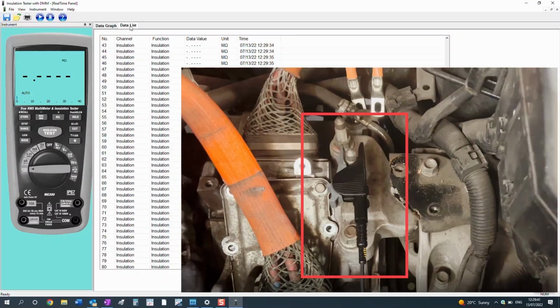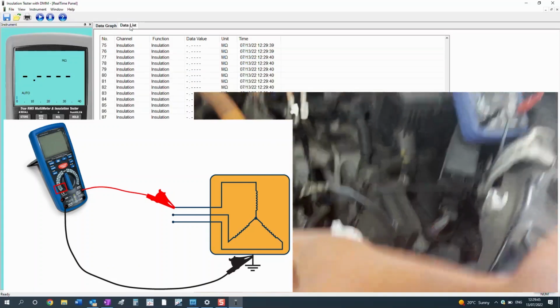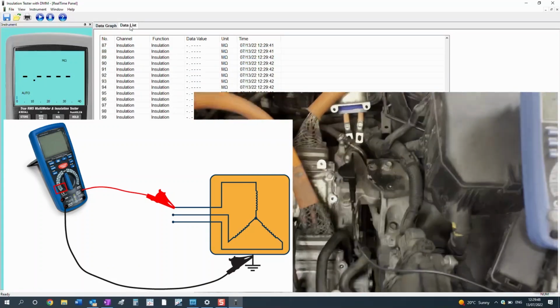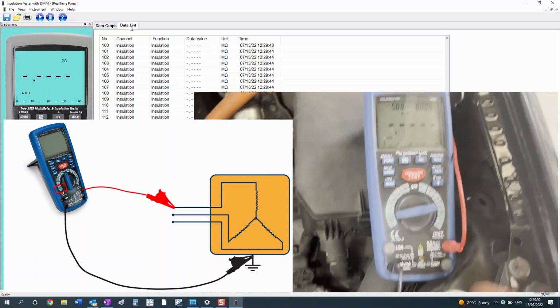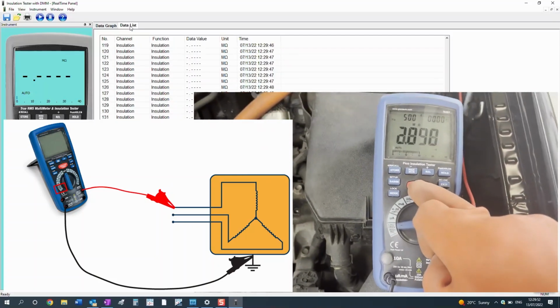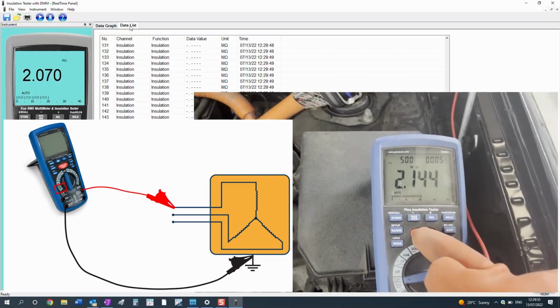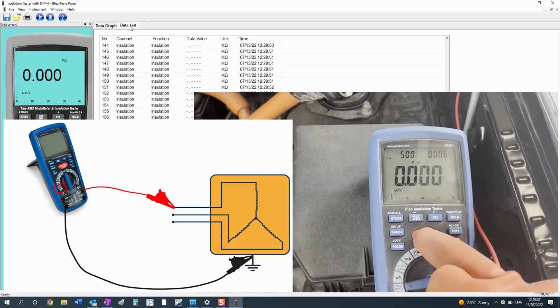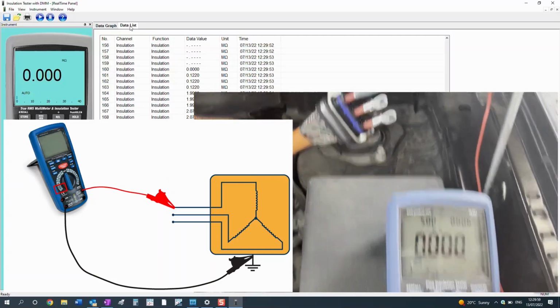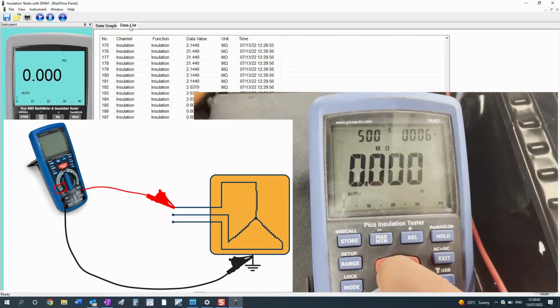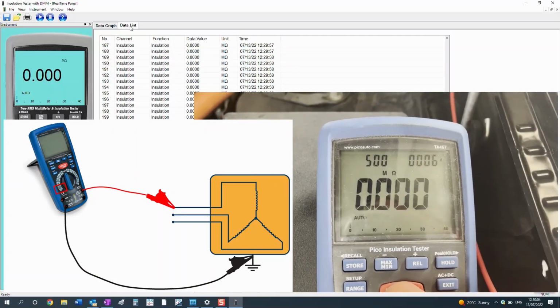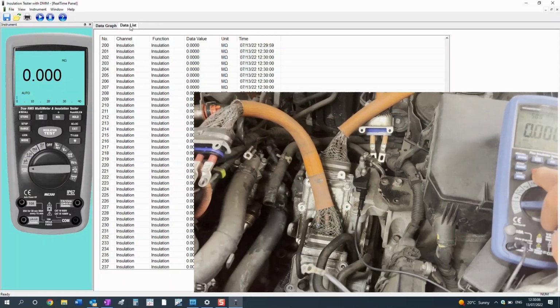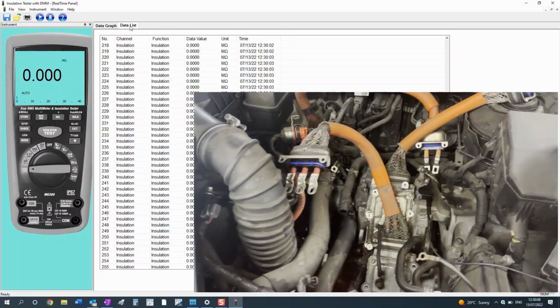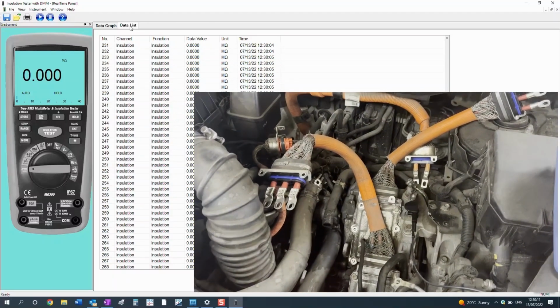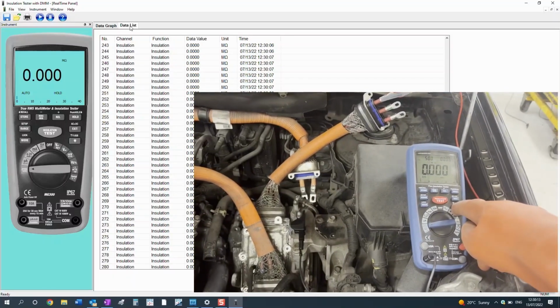Notice here that we are referenced to ground, or we're going to check for a short circuit to ground. We'll have our gloves on at this point because we are about to send 500 volts through the system, which is the correct voltage. Press and hold the test button. We see there that we've got a short circuit, and our test voltage is just 6 volts, even though we've selected 500 volts. So there is a short. And it's the same on each winding.